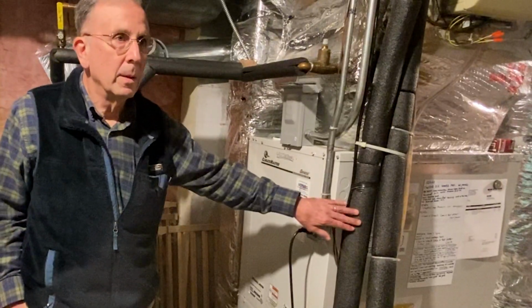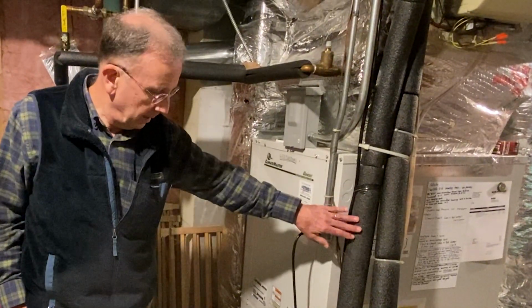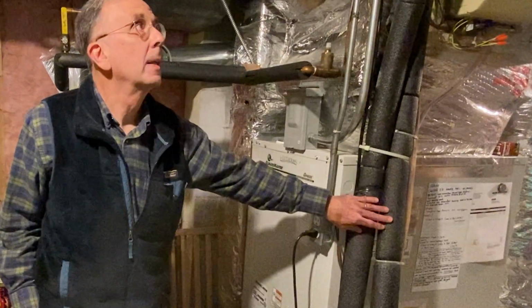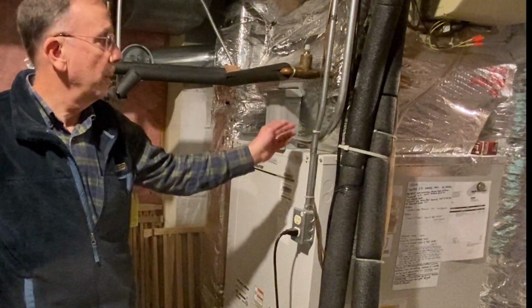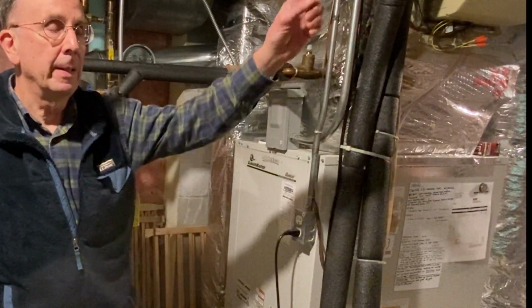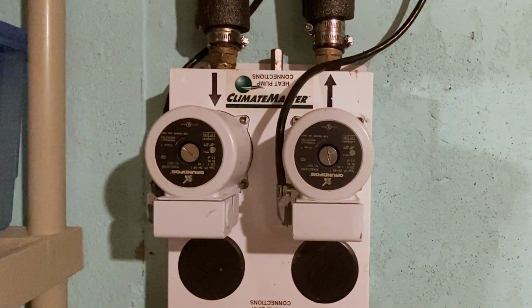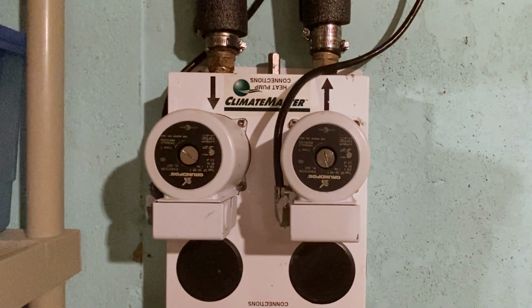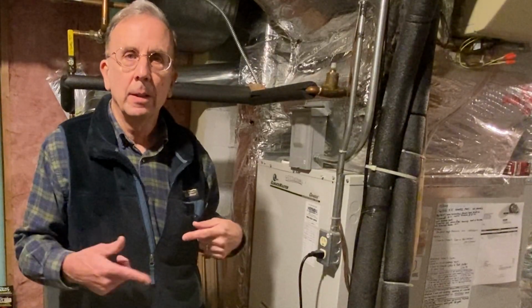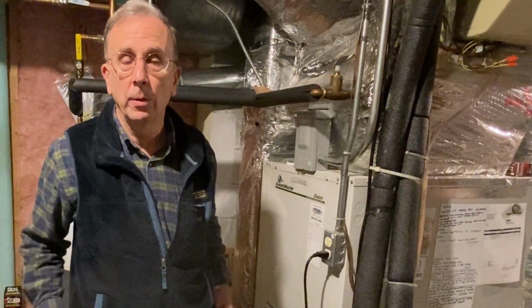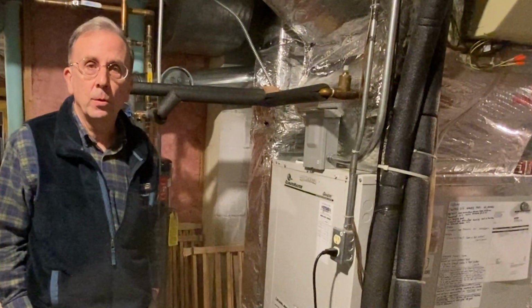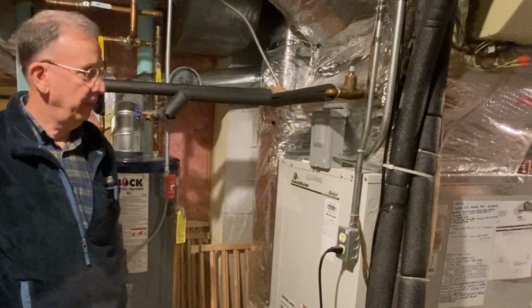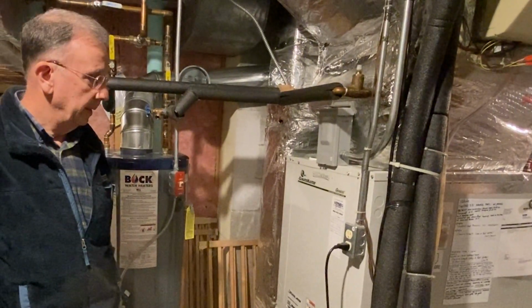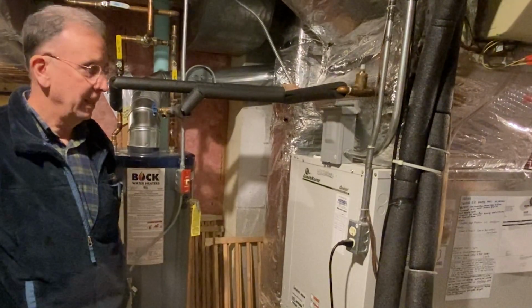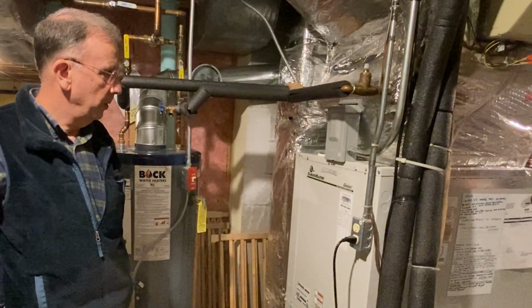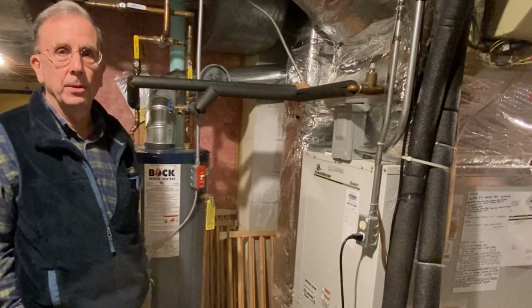So you can see the loop comes in and out through these tubes, but they come out of the heat pump unit and then go over to the wall. There are two pumps on each tube that keep the fluid flowing through the loops. We have two 400-foot wells, and so our total loop length is about 1,600 feet. It's not running right now, but over the 22 years, it's been almost maintenance free.